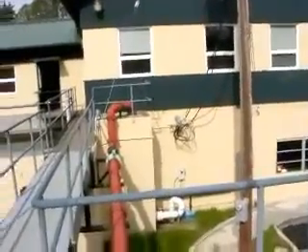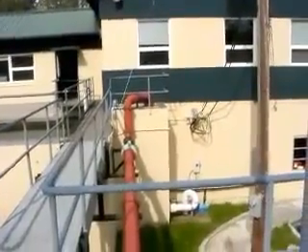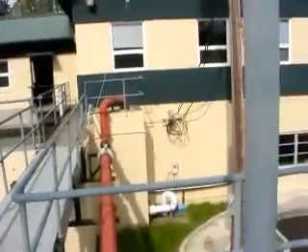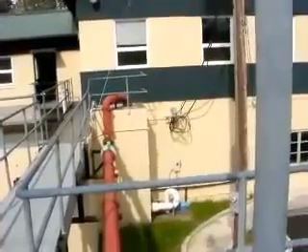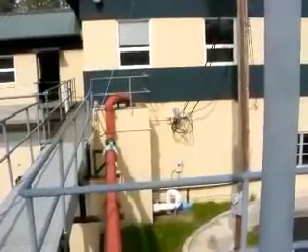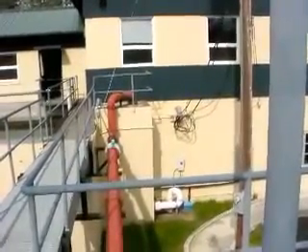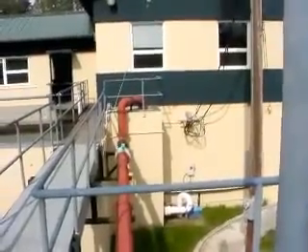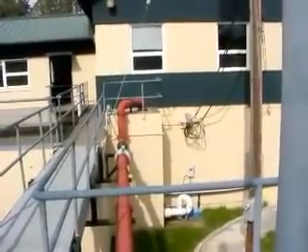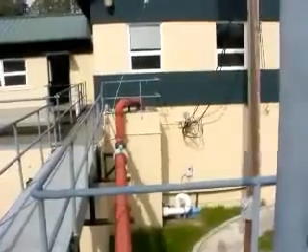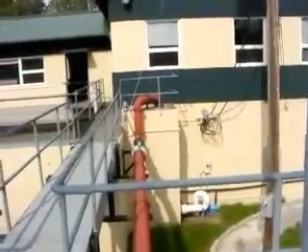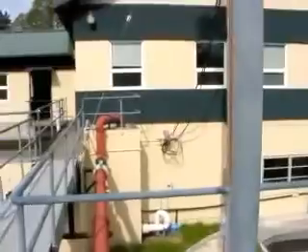So as it comes through the system, of course, we have the rapid mix. For our rapid mix, we use the pumps and reverse flow to mix. We no longer have mechanical mixers for rapid mix, and we just use the water moving around through here. But the pre-mix, it's flash mixing. Is it first the poly, then the alum, and then the chlorine? Correct.